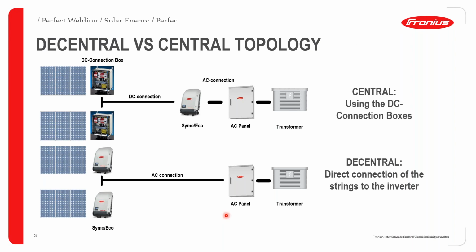Okay, now having a look at decentral versus central topologies, you can really choose with a SnapINverter whether you want to go for a decentral or a central topology. In the first case, we have a central topology. This is where your SnapINverter is located as close as possible to the AC side. So here we have really short AC cables, but then we have really long DC cables.